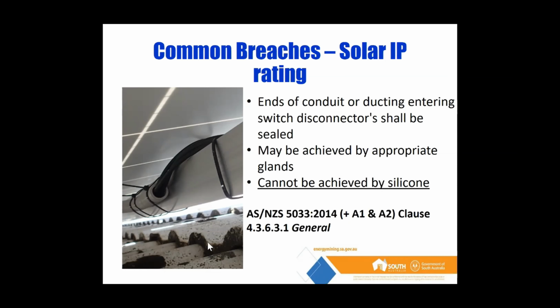So AS 5033 talks about how you can do that, and they give in one of their clauses that it can be achieved by appropriate glands. So in this case, a multi-hole gland would have been the way to go. And it also states that you can't achieve it by silicone. So it doesn't matter how much silicone you push into that conduit, it's not going to make it compliant.